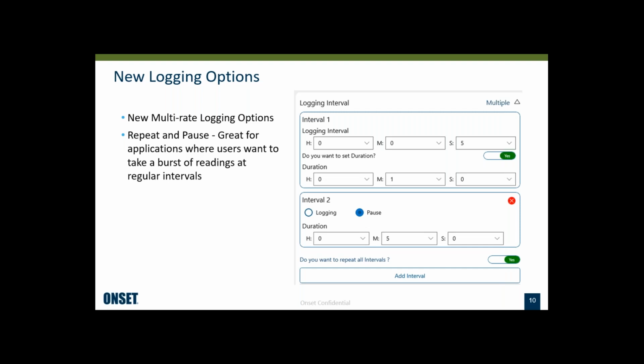One example is in wave applications. If they want to get a sense for how high the waves are, you can do a burst of readings to get the wave height, as well as use that to filter out waves if you want to just get the average water level. So you'd set that up as shown here on the screen with like a 5-second rate for a duration of a minute, and then the next interval can be a pause interval where it's not taking any readings for 5 minutes, and then the repeat option is on. That's the yes down here, so that it repeats that sequence until the memory is full.